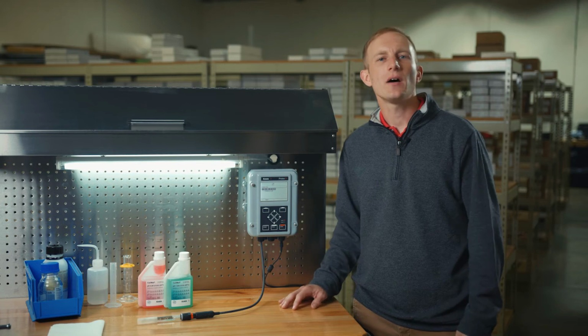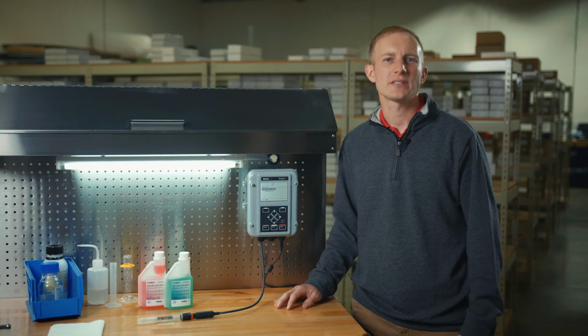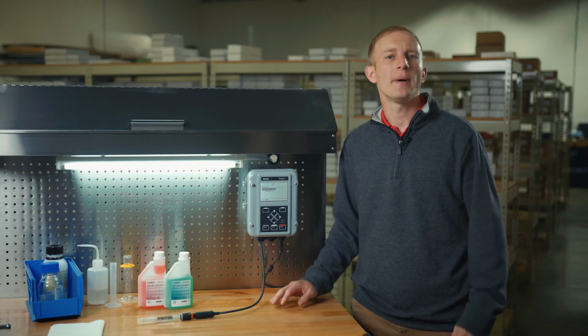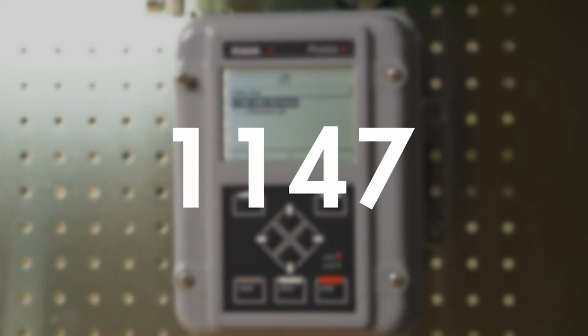If access to the calibration menu is blocked via a passcode, please note that the default passcode is 1147. Once within the calibration menu, we'll select the MemoSense pH sensor connected to channel 1 of our transmitter.